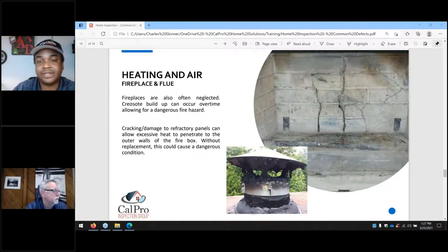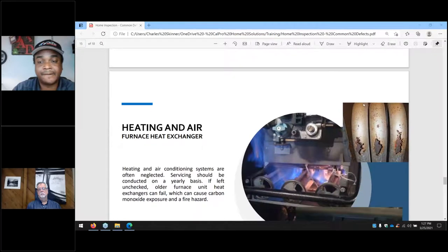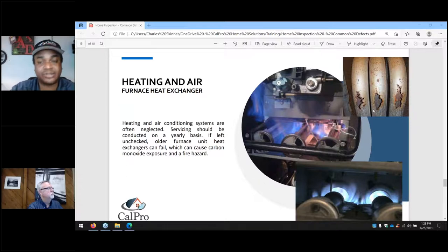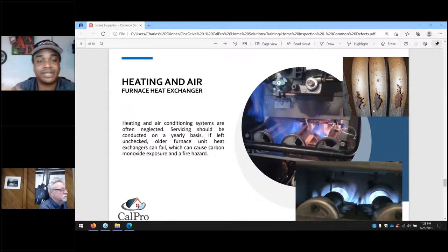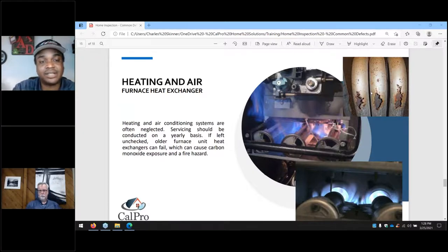Neglected fireplaces are very typical items — people use them but don't clean them. This is a cracked ceramic surround on the inside of the fireplace, which is pretty dangerous to use. A flue that hasn't been cleaned in an extended period of time is also a common issue. Regarding HVAC systems: regardless of whether it's operational, we have no way of knowing if the heat exchanger has failed. The way it works is that exhaust is blown through the heat exchanger and exhausted out through the flue — but if the heat exchanger is damaged, those exhaust gases are released into the airstream, which can cause carbon monoxide issues. There's no way to know there's a failed heat exchanger from a standard home inspection — someone needs to come in with a camera to view the inside of the heat exchanger. That can be done by a licensed HVAC company.